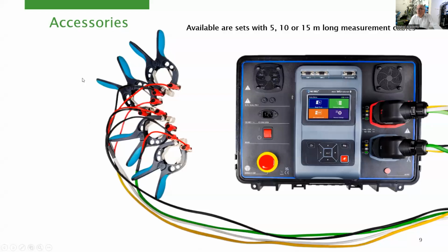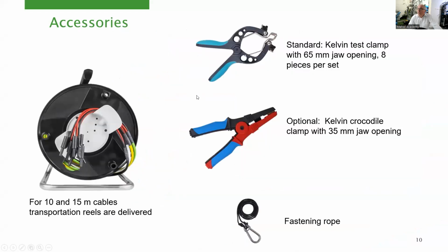The instrument is equipped with very simple accessories. It comes with 3 different sets of cables, 5, 10 or 15 meter long cables. The rest of the accessories are almost the same. We always use these 2-wire cables, which makes it possible to perform the 4-wire measurement technology. The clamps are always these Kelvin clamps for big transformers with big terminals. The jaw opening is here up to 65 millimeters.